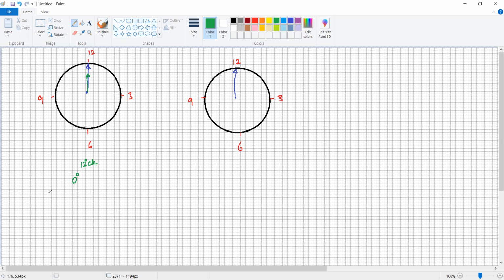So say for example, the connection is star star 0 degree. It means that the vector group is Yy12 connection, isn't it? This is the Yy12. Similarly, if the secondary winding is 180 degree apart, the phase shift is a 180 degree.